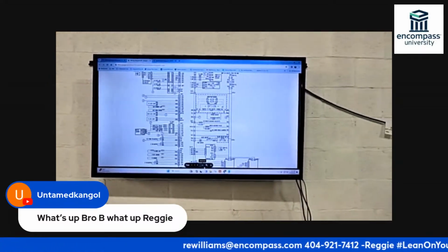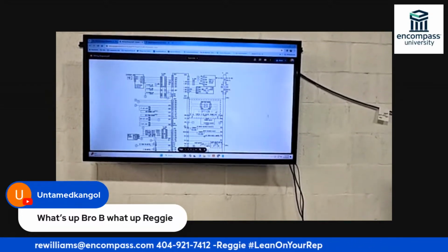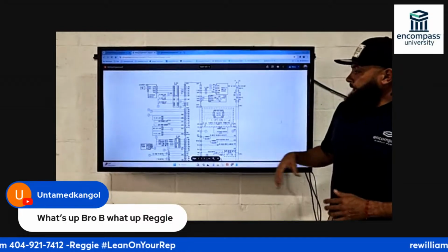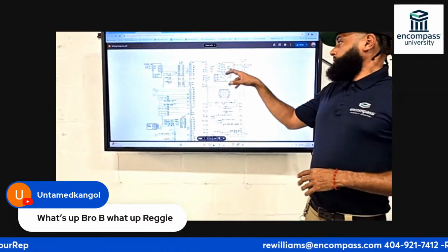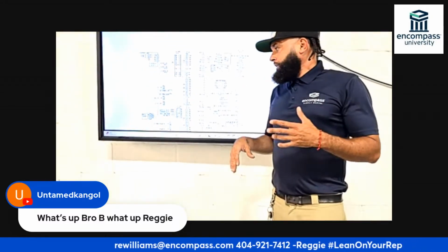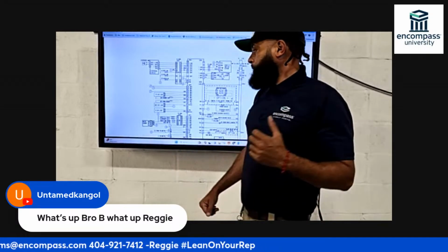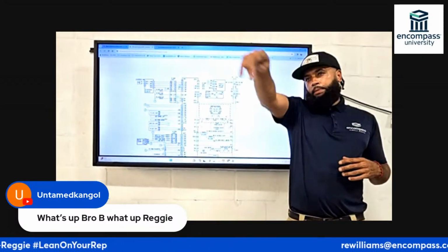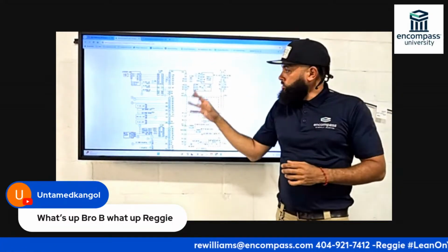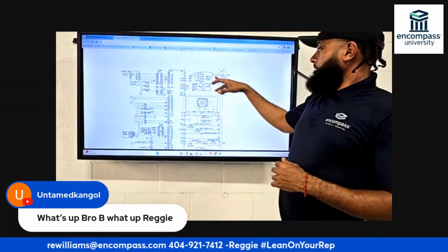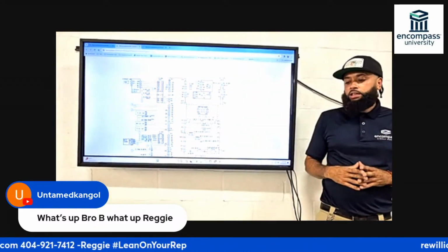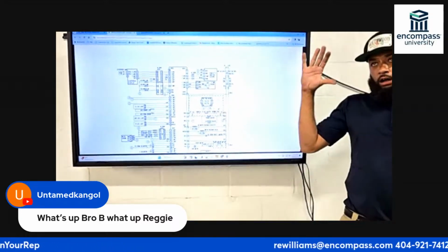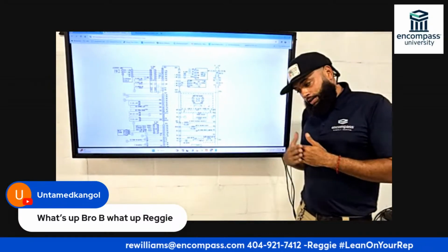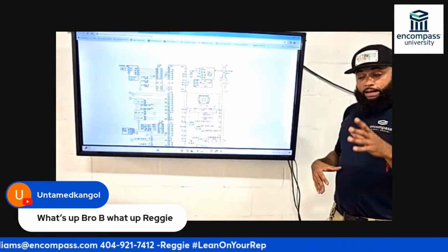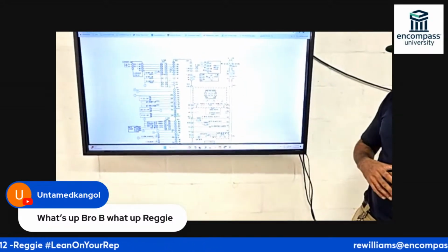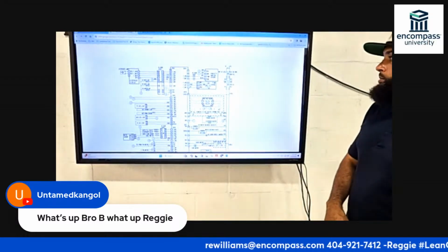I want to talk about the components in the unit, some of the components and what they do. The ambient sensor detects humidity - a lot of these refrigerators put a sensor in the ambient compartment, typically right by the upper hinge. If you remove the upper hinge, you'll see a little sensor there, that's the ambient sensor. Its purpose is detecting the outside temperature of the box and sending that information to the board. That ambient temperature has a big part in the condenser fan's movement and how often and how much it runs.